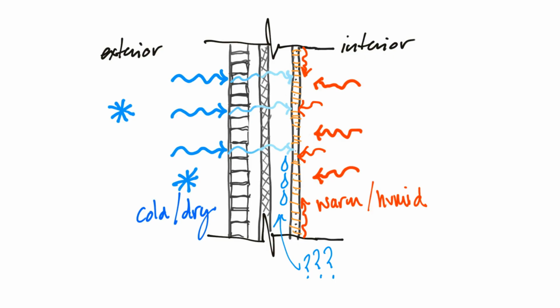I think if you look around, you'll see frequently diffusers along large expanses of glass to heat and cool that area, or baseboard heaters, radiators in older buildings, because glass has such poor thermal performance, and you're trying to overcome that heat loss and that cold that you're getting on the inside face of your glass. You don't want condensation there in the same way that you don't want it on the inside face of your exterior wall in other places.